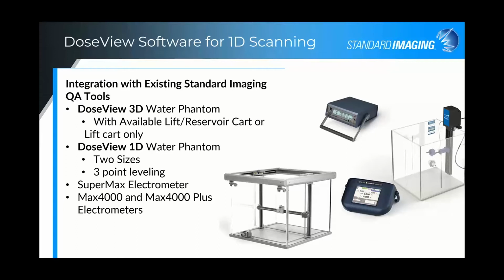Our Doseview 1D Phantom has two sizes available, a larger and a smaller tank, as well as includes 3-point leveling, the ability to easily set up and maintain the memory of the position of the chamber as you go outside, disconnect the Phantom, and then reconnect it to either our Supermax or our Max 4000 electrometer or our Max 4000 Plus. So it becomes an integrated system with our software utilizing those electrometers.